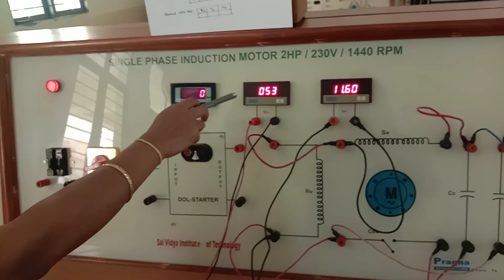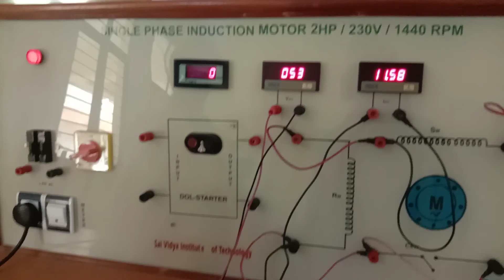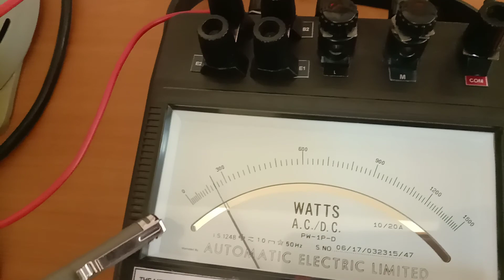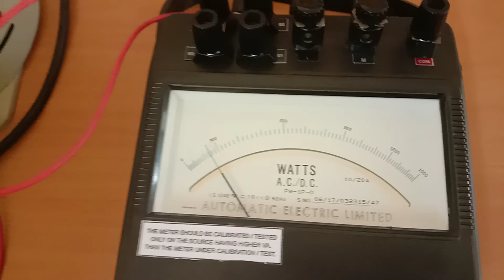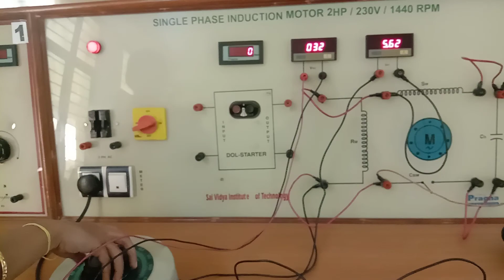So here we can take down the corresponding readings. This reads the ISC, that is 11.5, and the VSC, that is 53 volts, and the wattmeter reading will be around 240, multiplied by the K constant. So again we have to bring back this auto transformer to the minimum position, and we can switch off the supply.